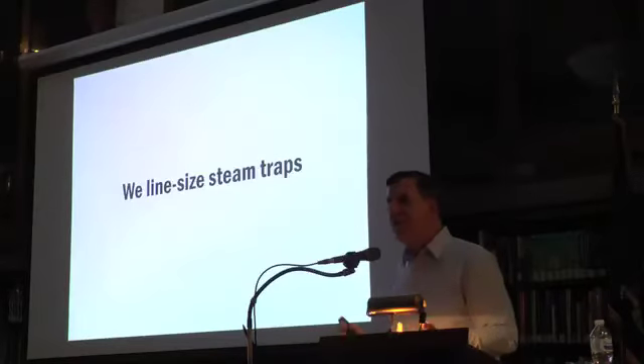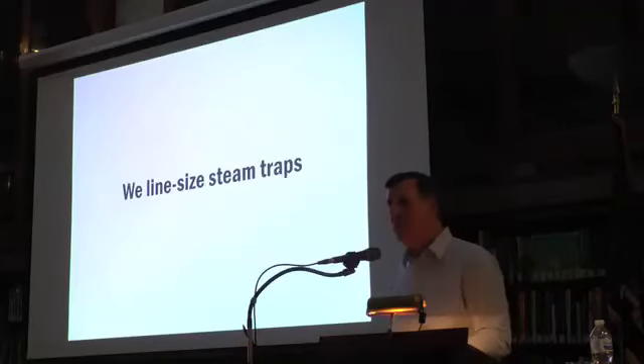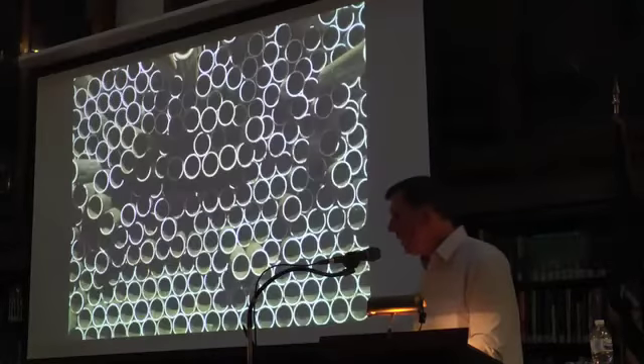John, what size was that? Is John still here? Okay, he's like, I think it was like a 2.5-inch trap at the end of this system. And I looked at that, and the reason why it was a 2.5-inch trap is it was a 2.5-inch pipe. There's now a 3/4-inch pipe doing the same. A 3/4-inch trap doing the same thing, and it's oversized. So traps don't need to be or should not be line-sized, and when we size them that way, we're going to be wrong every time.